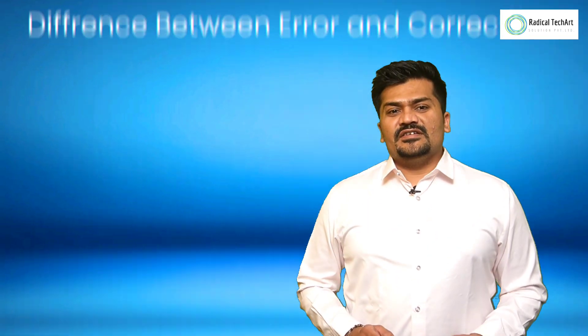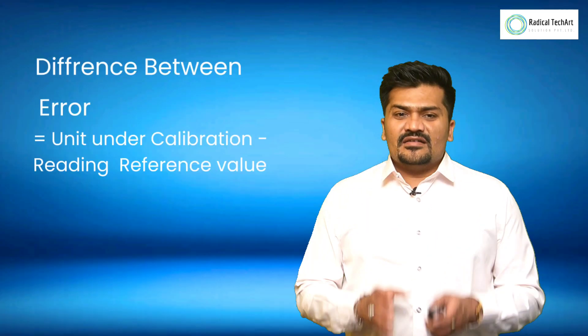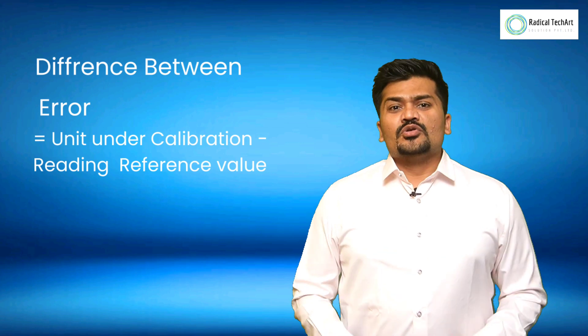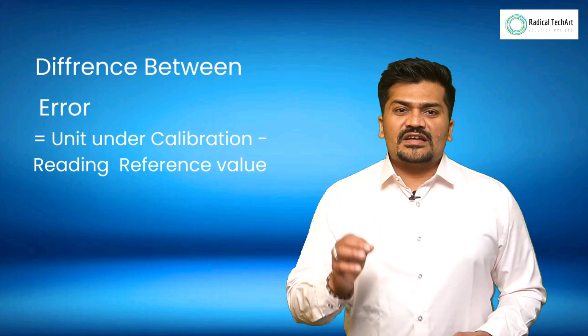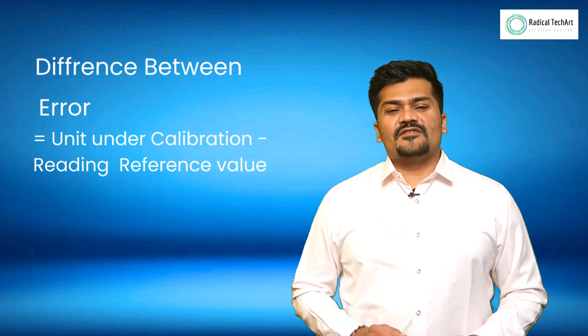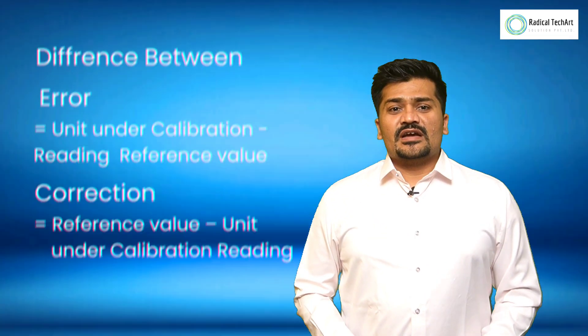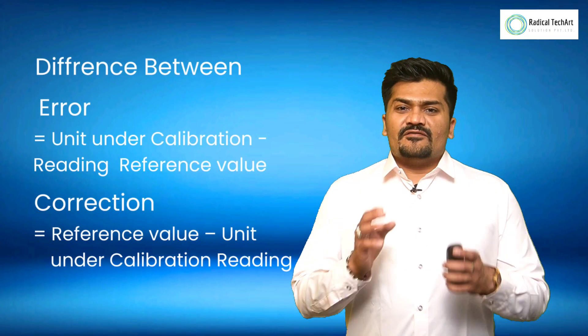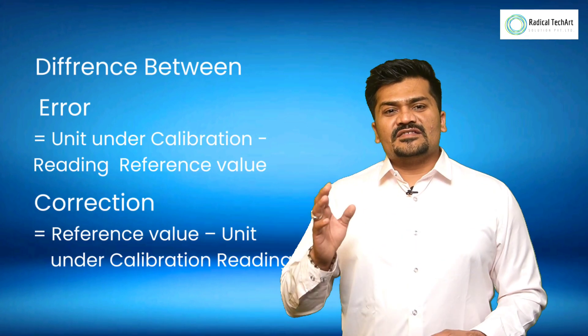The formula for error is: Error = Unit Under Calibration reading minus Reference value. And the correction is: Correction = Reference value minus Unit Under Calibration reading.